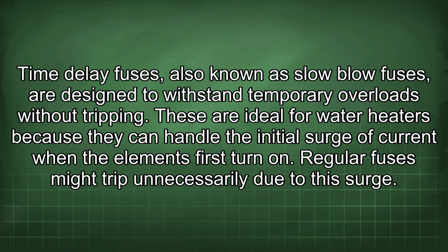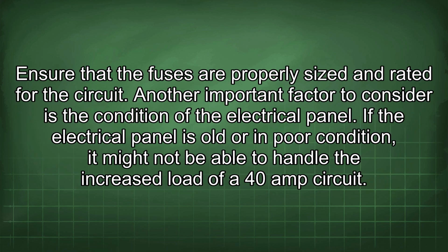Also, consider the type of fuses used in the fuse disconnect. Time-delay fuses, also known as slow-blow fuses, are designed to withstand temporary overloads without tripping. These are ideal for water heaters because they can handle the initial surge of current when the elements first turn on. Regular fuses might trip unnecessarily due to this surge. Ensure that the fuses are properly sized and rated for the circuit.